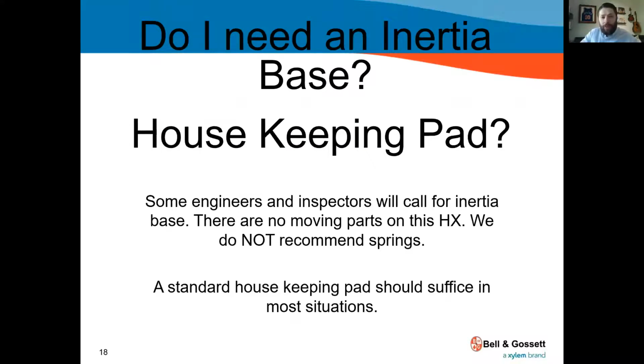So I get this a lot. Do I need an inertia base under my plate and frame heat exchanger, housekeeping pad? What do we do? I've been in this conversation a lot of times. The IMC doesn't get specific. It's going to be local to your building code where you are. So some will call for an inertia base.